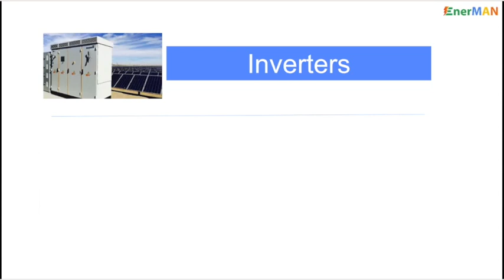Communication port not working is one of the major issues we've seen, and it takes a lot of time to be rectified, because the response from the inverter team goes back and forth. They say the port and everything is fine, the inverter is generating, because for them the communication port is of the last priority. As long as the inverter is performing, they're okay with that. So the challenge here is the communication port not working.